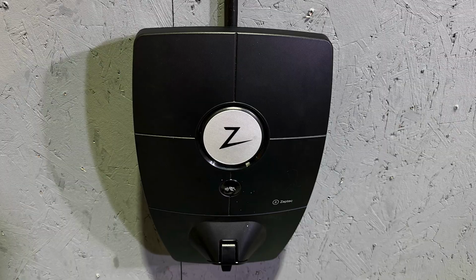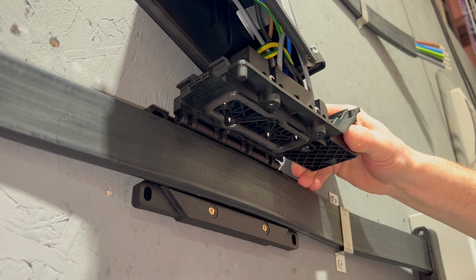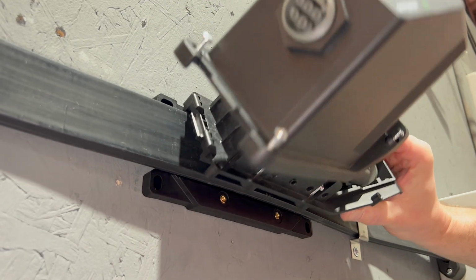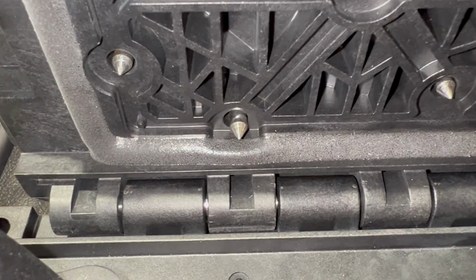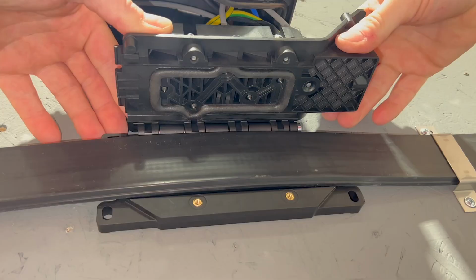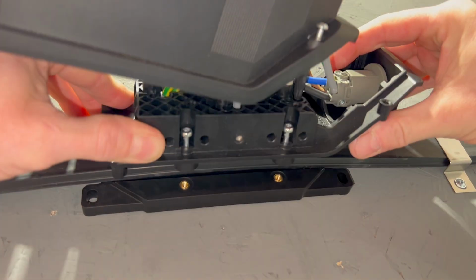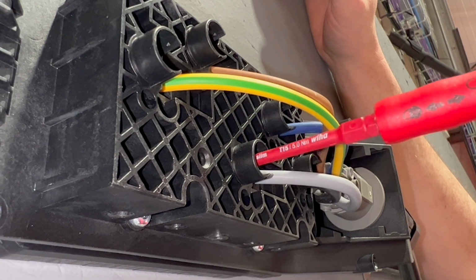The ingenious aspect lies in the method of establishing an electrical connection to the busbar cable. After positioning the tap-off box around the cable, there's no need for any cutting or terminating any cables. Instead, by driving these insulation piercing screws directly into the cable, you effortlessly complete the connection.